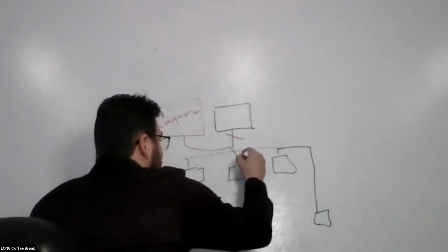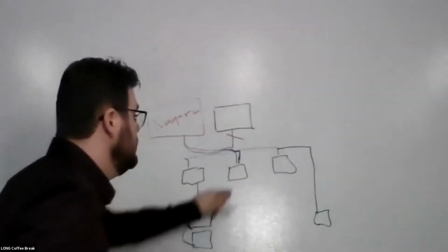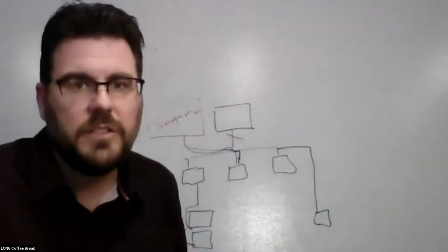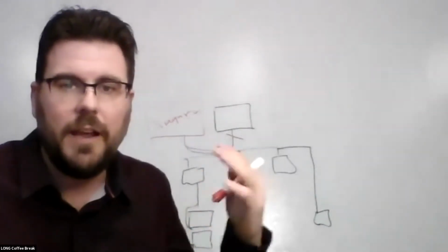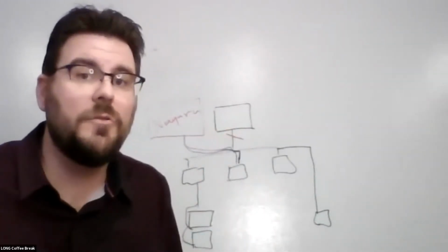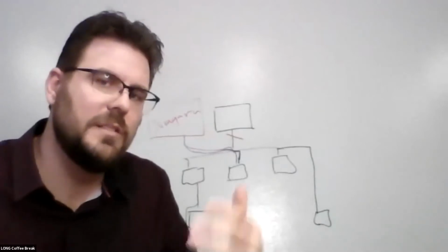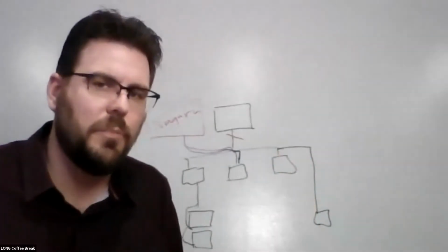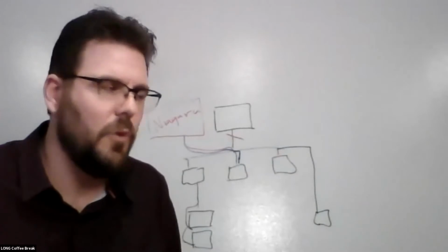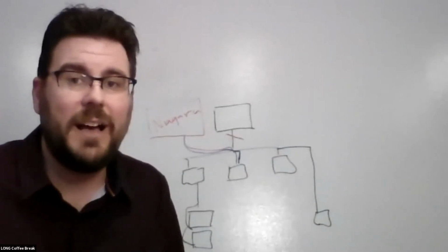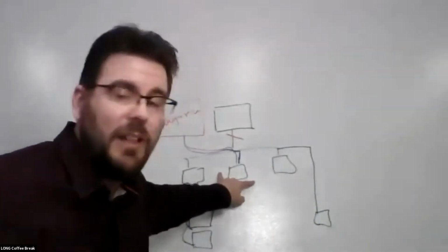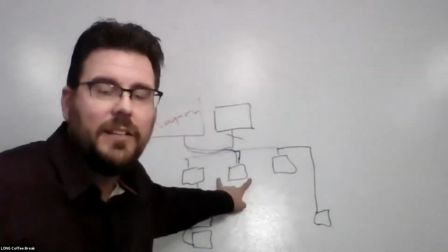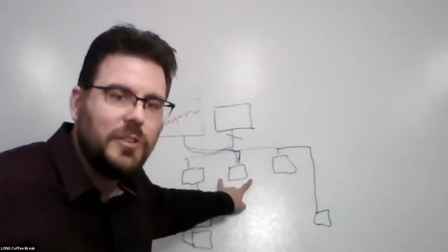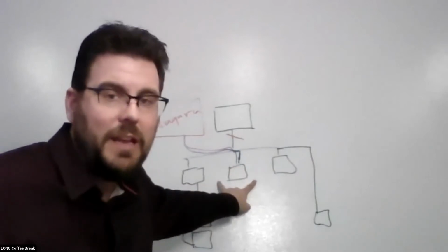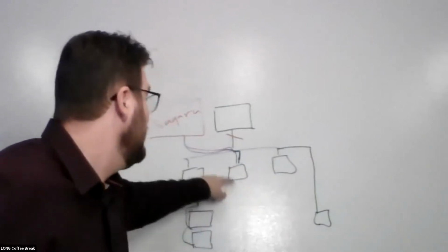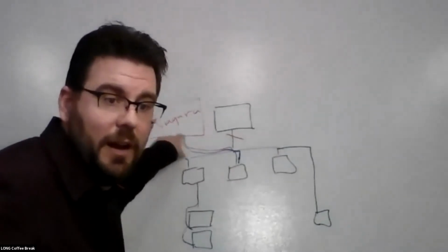Right here, from an older protocol to BACnet. So you can get it to BACnet MSTP or IP just through firmware, because it's newer technology, but it was still using older proprietary protocols in the firmware. Sometimes that's a very economical way to extend the life cycle of keeping this as infrastructure, just by doing a firmware upgrade and paying the original manufacturer to do that. And then now you can pick it up at the top end.